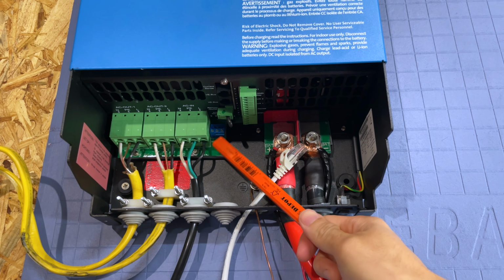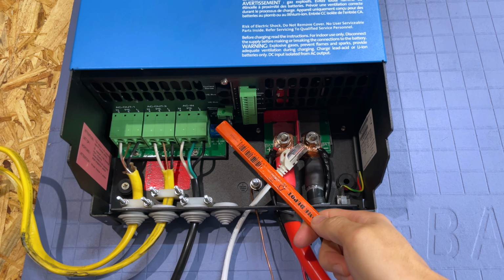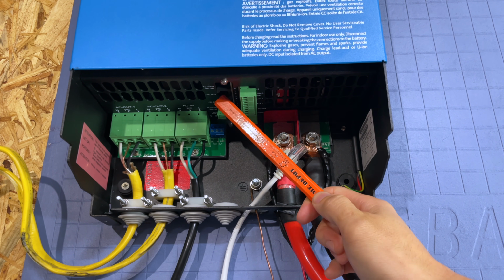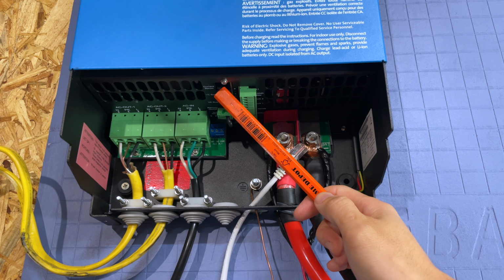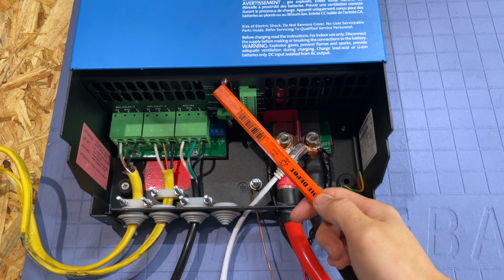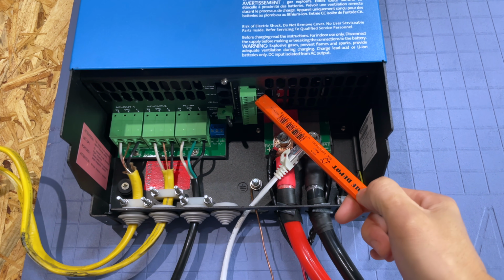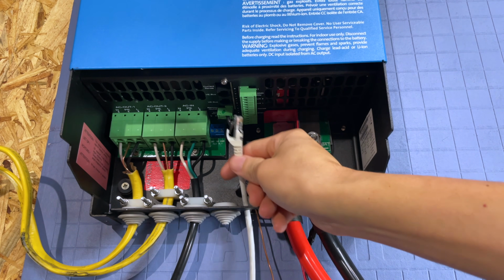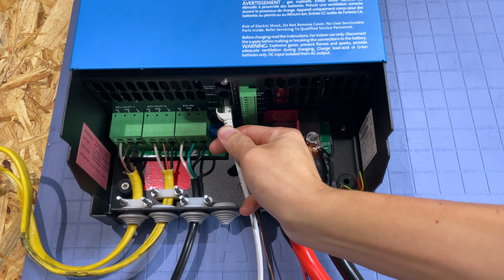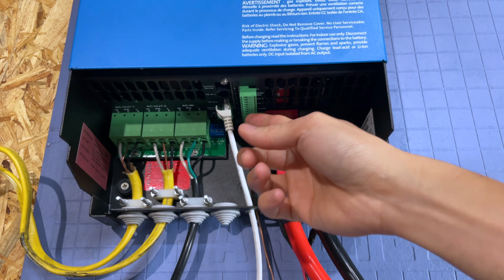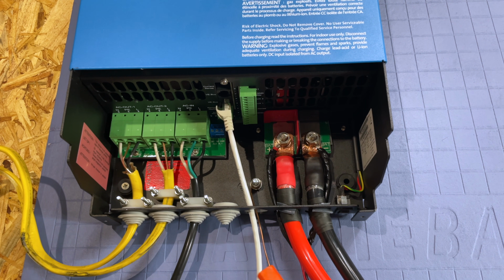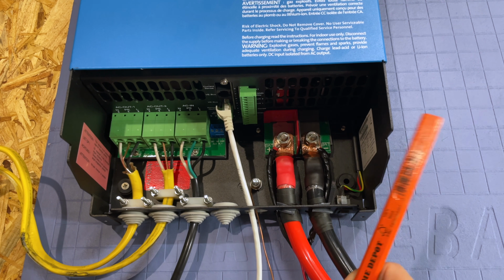If you look here, there's a bunch of relays you can use. There's a jumper you can use, VE bus, a current sensor, a 3.5 millimeter port that you can use for current sensors here. There's other dry contacts here that you can use for all kinds of fun stuff. White Ethernet cord. It's a standard Ethernet RJ45 cable. You plug in the VE bus and you can also plug into the Cerbo GX, and it sets up communication between this inverter and the Cerbo GX.